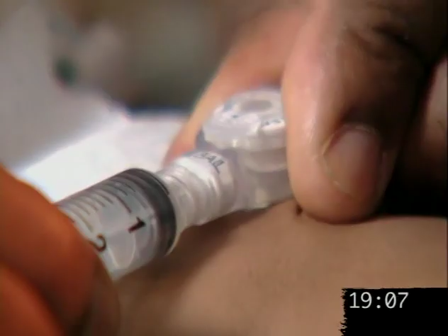Sometimes the water in a balloon may have evaporated or leaked and will need to be replaced. Check the balloon and add the difference if needed. Normally, 3 to 5 cc's of water is necessary to secure the balloon inside the stomach. Never use air to fill the balloon. It is acceptable to add 1 to 2 cc's of water to increase the balloon volume. Never exceed 5 cc's because the balloon may break.